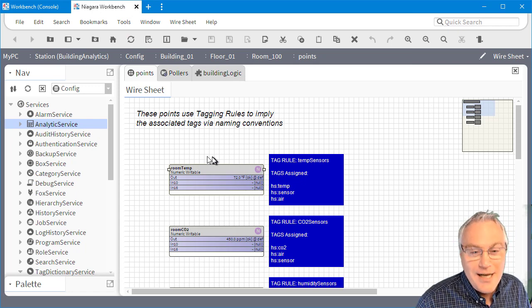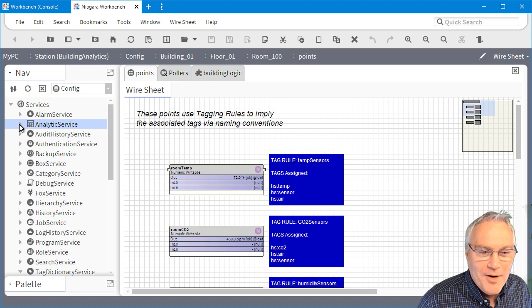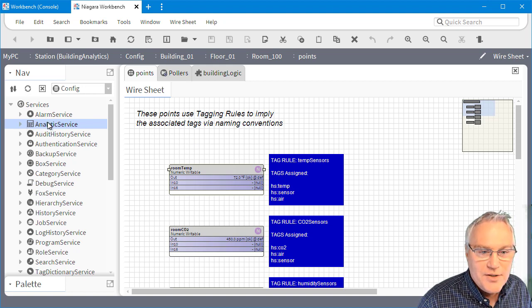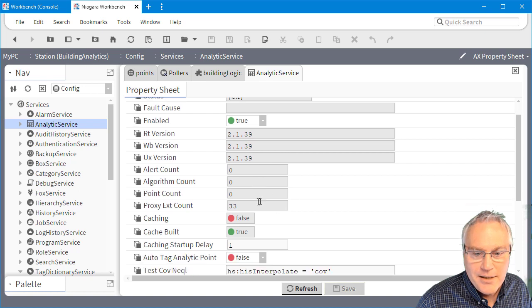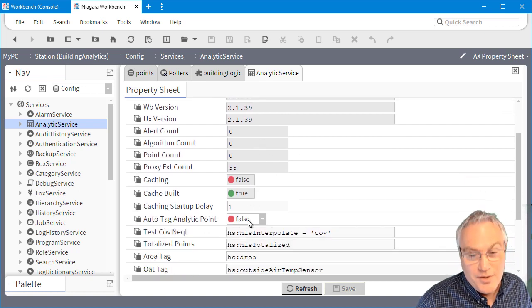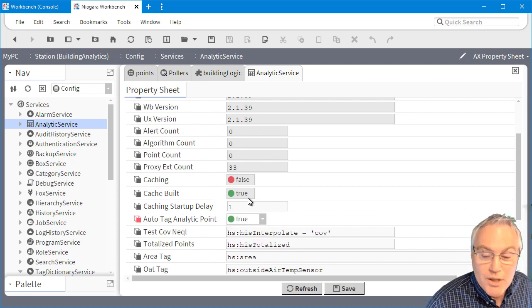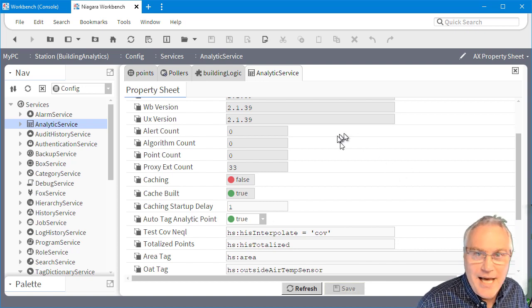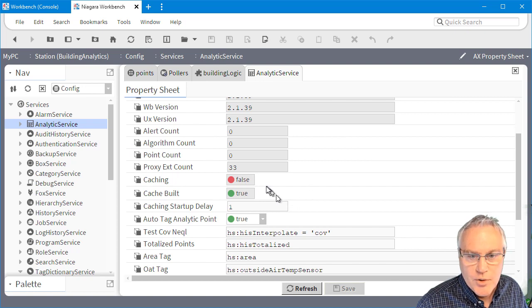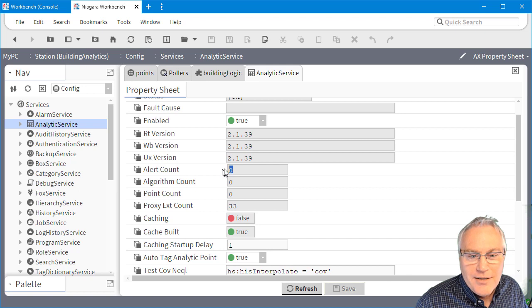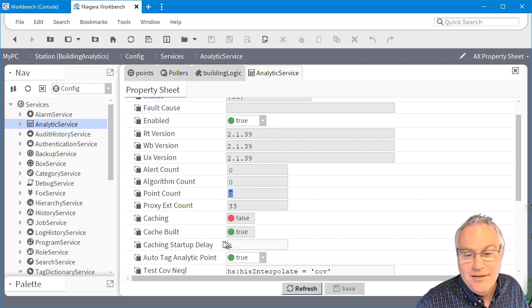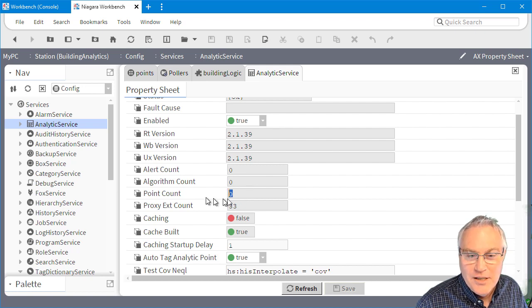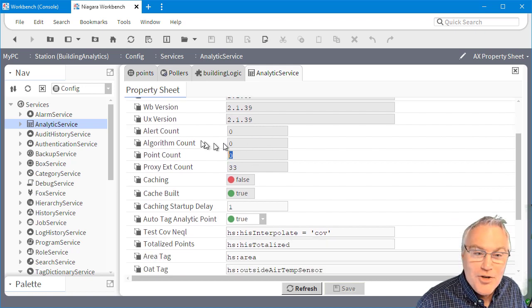Because you could waste hours if you don't understand what's happening. So what I'm going to do is let's take a look at this analytic service because what I want is I want those A colon A tags to apply automatically. And you'll see down here, this auto tag analytic, it defaults to false. So I want to make sure it's set to true so that it does that work for me. Otherwise, it's kind of tedious. I'd have to add that tag every single time I added a point that I'm going to reference or look for. So I'm going to do that. Notice 33. Another telltale sign after I've done this recording twice is that these are all zero. So that's another clue that your A colon A tag doesn't exist because I should have a point count of actual points that are being adjusted.